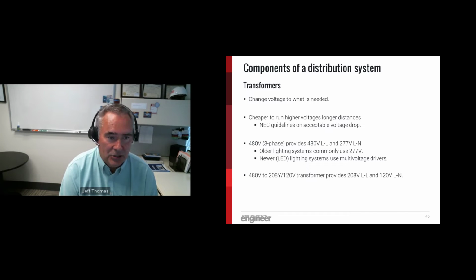And this is basically just due to the I²R losses in conductors. So if we get the voltage up higher, the current stays lower, and our conductors become less of an issue. The thing to remember is whether we're at 480 or 208 or 120, all of our conductors are rated the same. They're all 600 volt conductors. So we don't save any money by going to the lower voltage. We actually save money running at the higher voltage because the conductors are smaller.